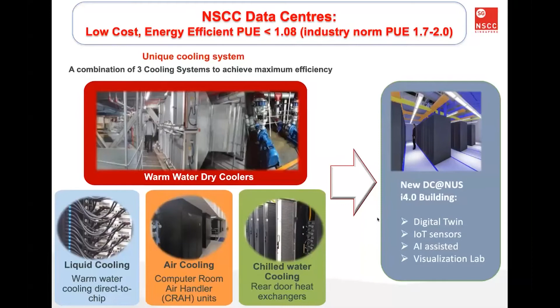Going forward, our warm water dry cooler system, which saved at least 50% of the power needed for cooling, will lend its way to our next generation data center, which we are in the process of building. That will include digital twin, IoT sensors, and AI-assisted systems that will help us drive the PUE even lower.